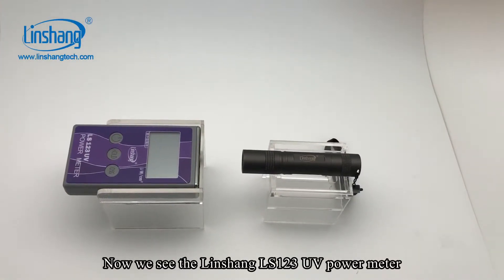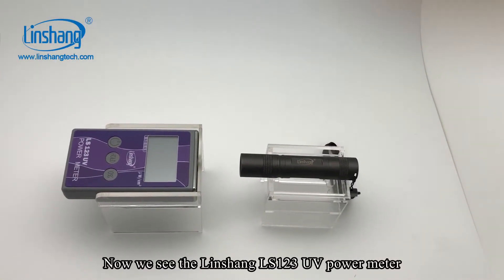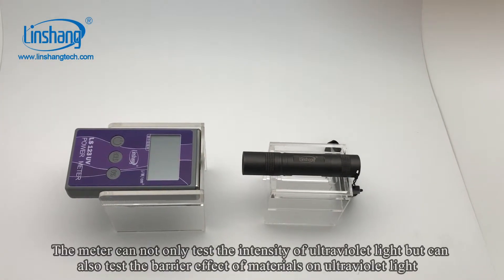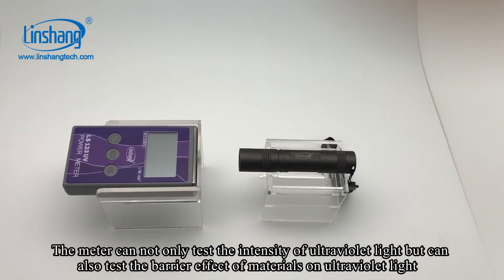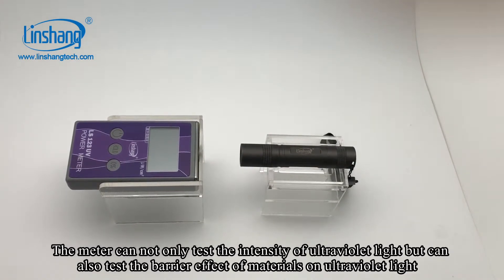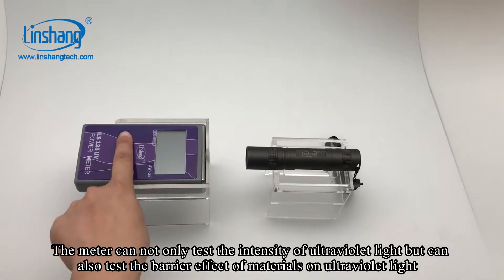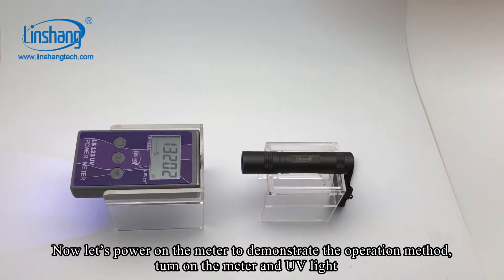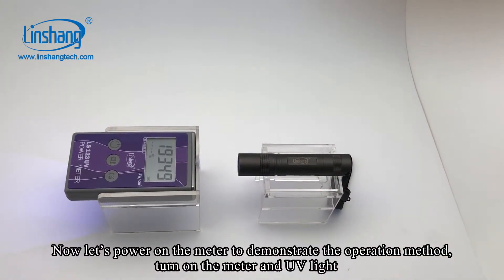Now we see the Linshang LS123 UV power meter. The meter can not only test the intensity of UV light, but can also test the barrier effect of materials on UV light. Now let's power on the meter to demonstrate the operation method.